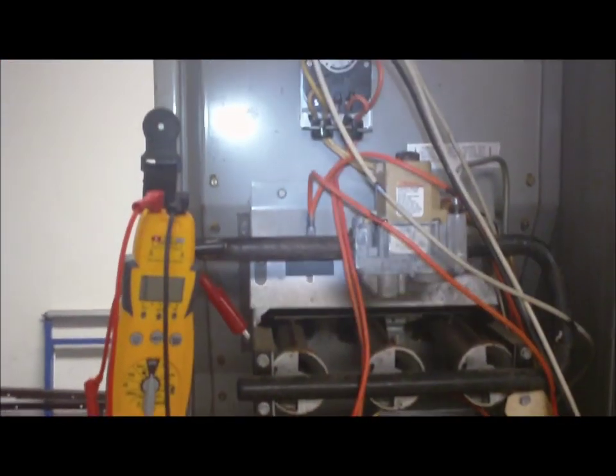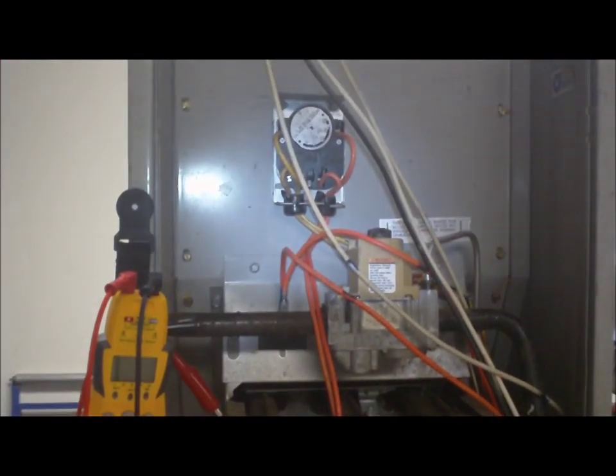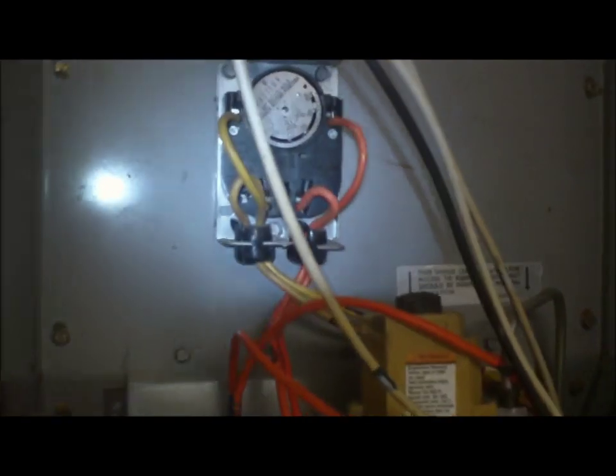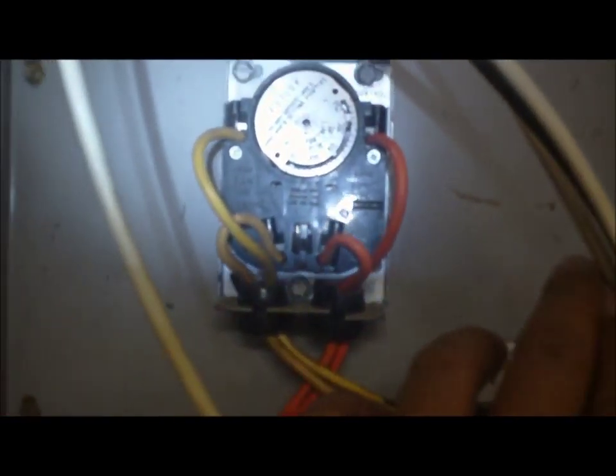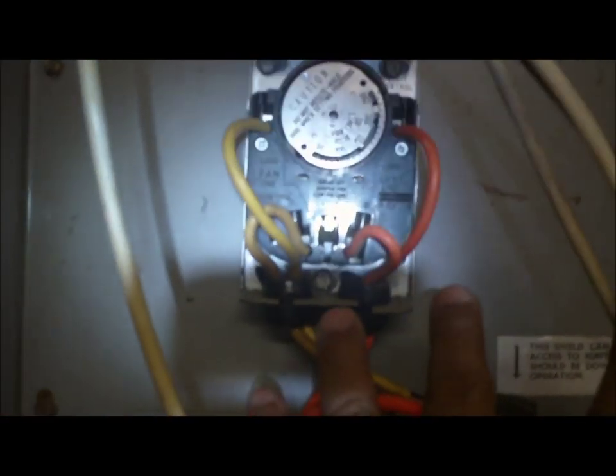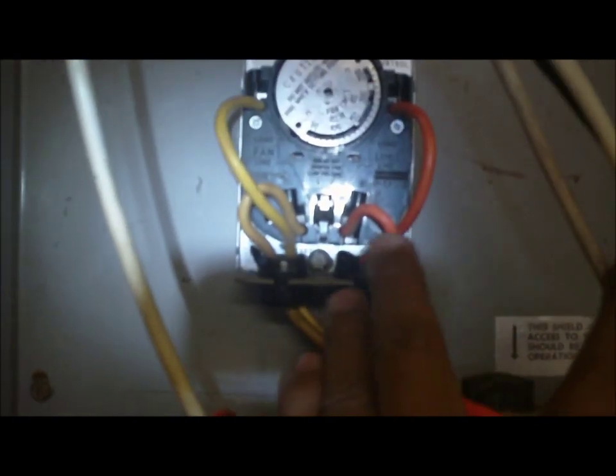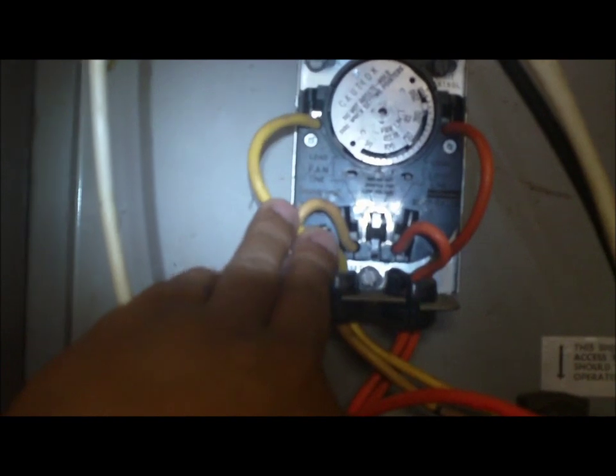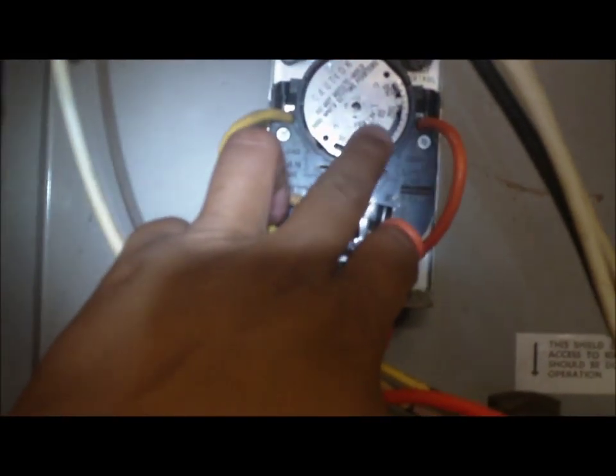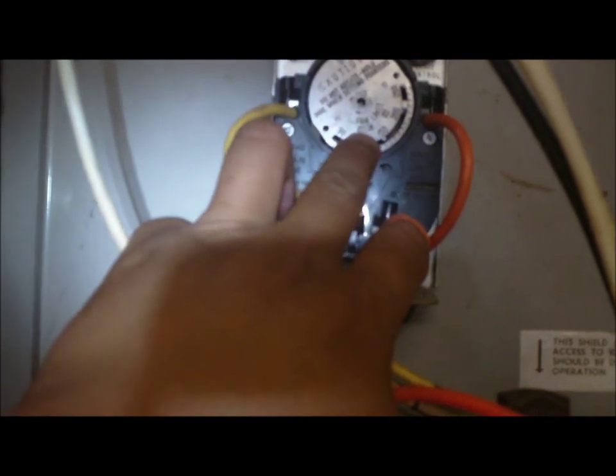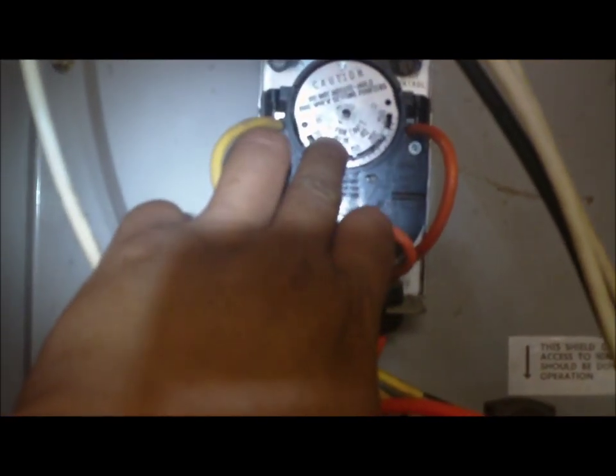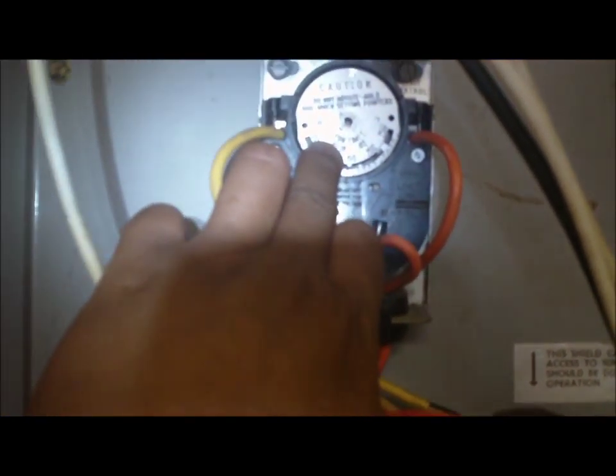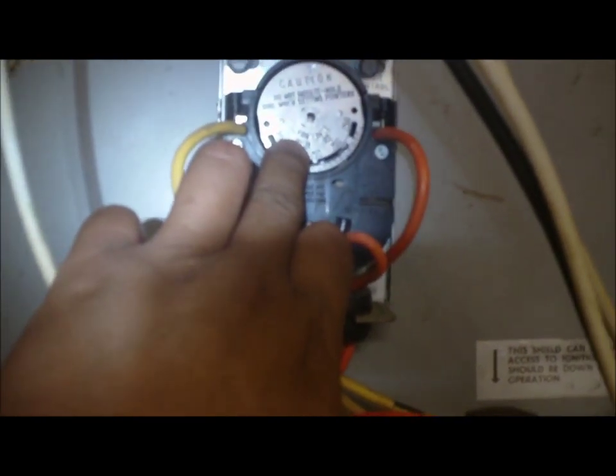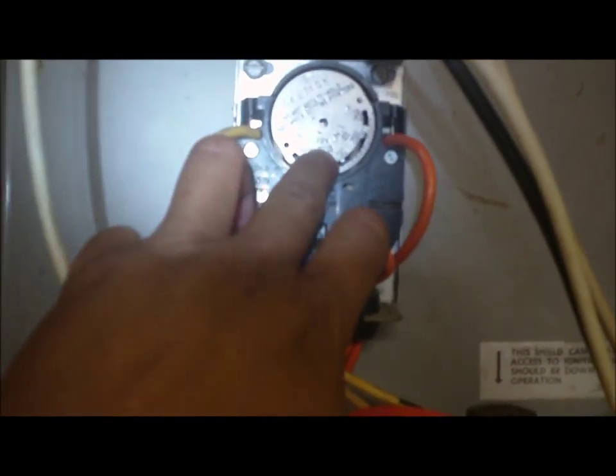Like I said, this is a combination fan limit switch right here, which is wired high and low. This is your low voltage wires for 24 volts, and this is your 120 volts. This is your dial. This one is set at 150, so that it will click and it will turn on your blower motor on low speed.